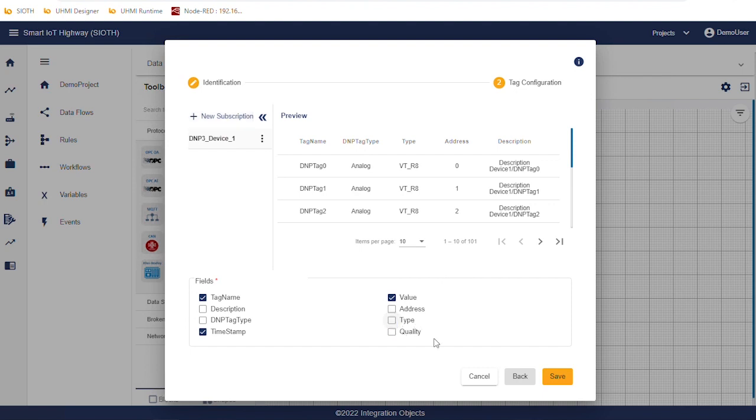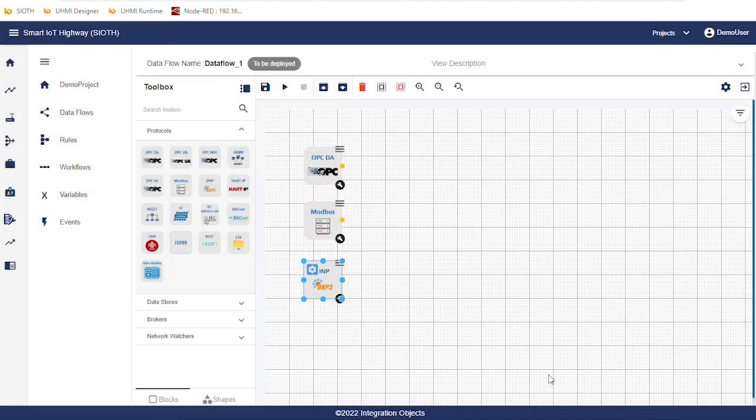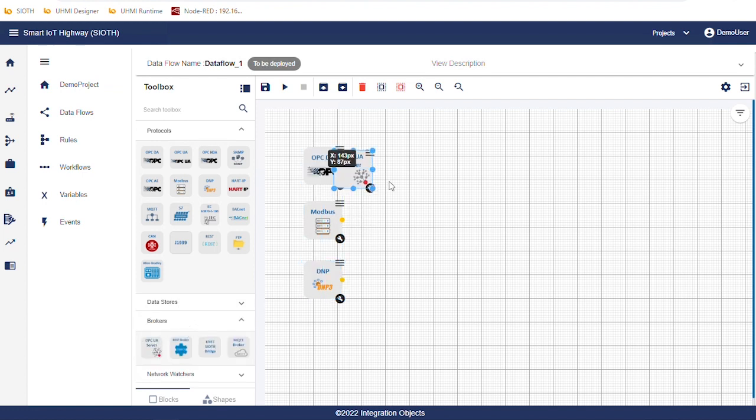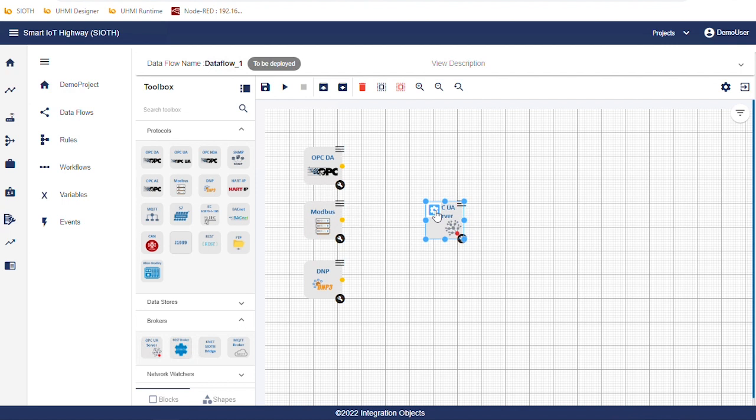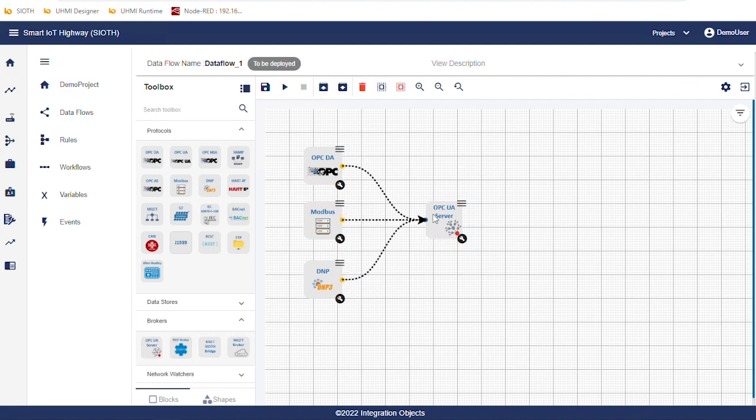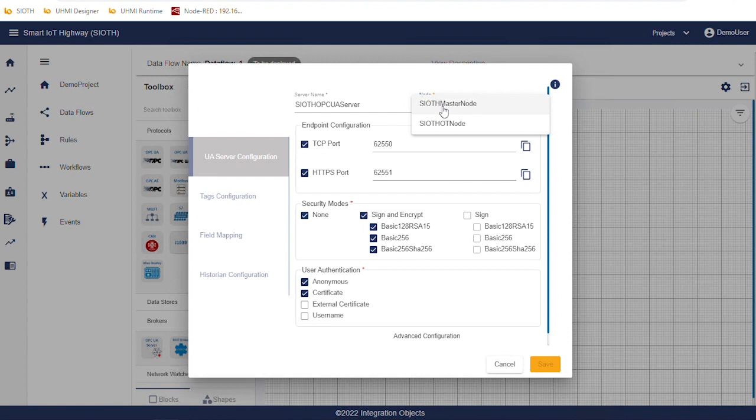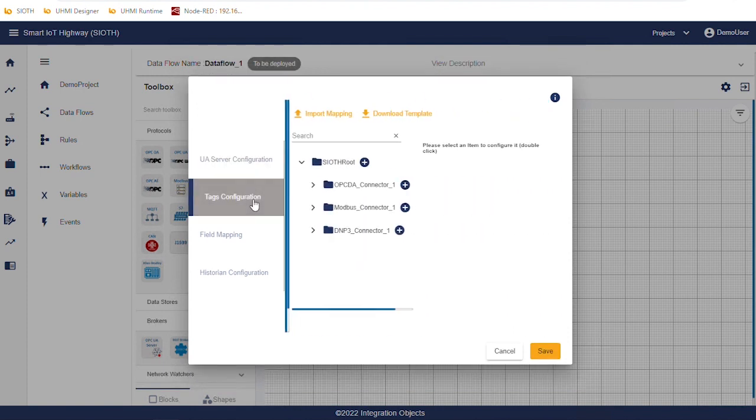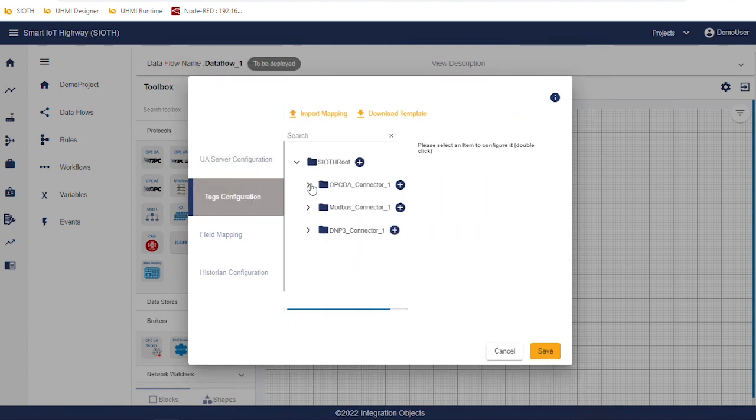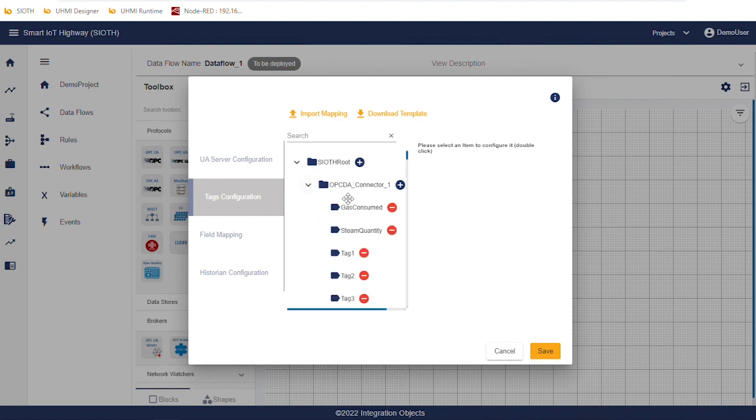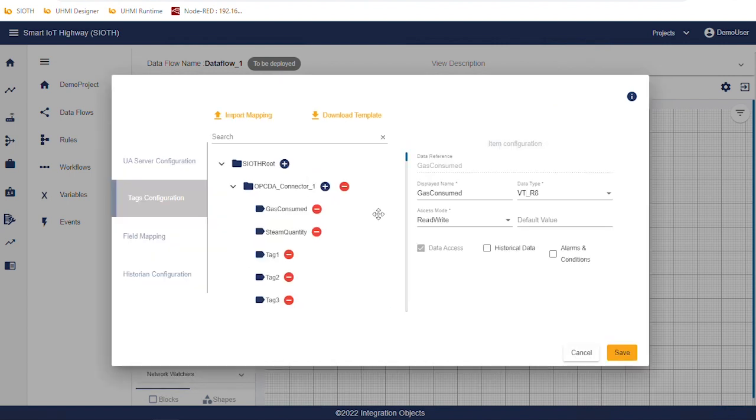Now, we will configure the destination's connectors. We start by SIOTH OPC UA server. Drag the OPC UA server block from the toolbox and drop it in the workspace. Then, link the configured source connectors to its input port. Click the settings icon, select the node and then click on Tags Configuration. You will notice that all of the configured tags are added automatically to the SIOTH OPC UA server. We can also enable historical data for the OPC UA tags.